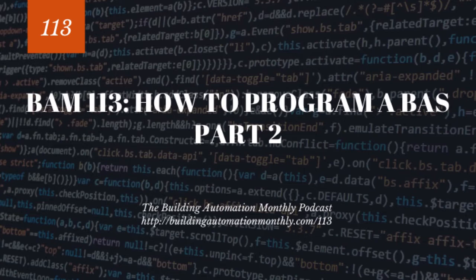So basically, it could say, hey, stage 1 comes on when you've been above 24% for 5 minutes, and then it runs for 5 minutes, and when it goes below 20%, it goes off, and it stays off for 5 minutes. And that can confuse a lot of people. They're like, hey, I'm at 70%, but none of my stages are turning on. Well, that's because stage 1 is off. And stage 1's min off time is off.